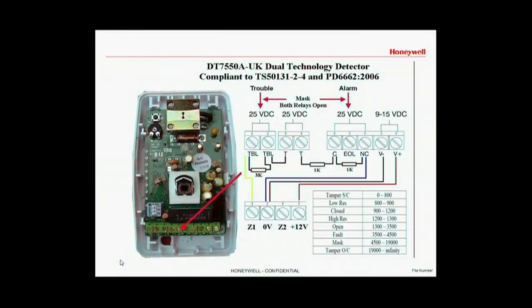This is a typical schematic of a Honeywell grade 3 anti-masking detector that doesn't have a separate mask relay. Under normal circumstances we read 1K in the line which is closed. In an alarm condition we read 2K. In a fault condition we read 3K plus the 1K which is 4K. And in a mask condition we open both the alarm and the trouble relay, so we read 5K.